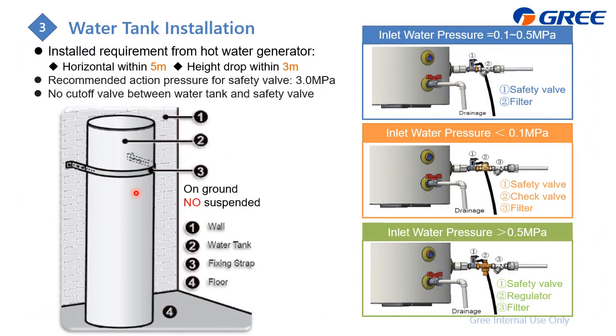Water tank installation. For this one, the water tank, we don't require you to buy from Gree, but just follow our requirements to install the water tank. It's okay. And first, this water tank should be close to the hot water generator, which is horizontal within 5 meters and the height drop within 3 meters.